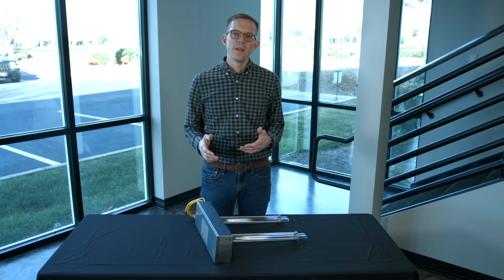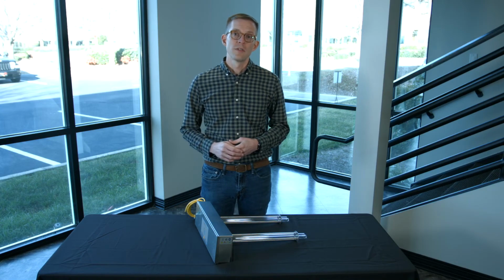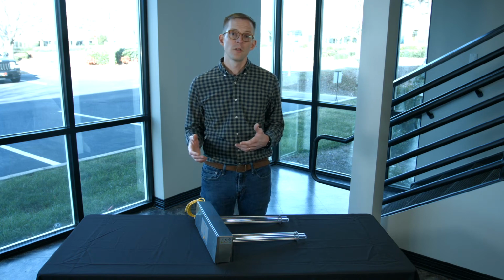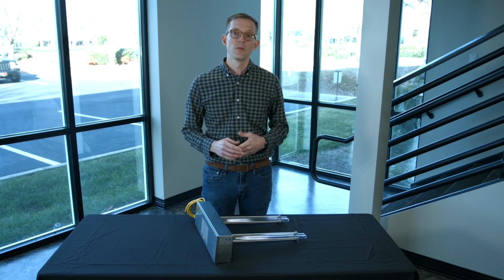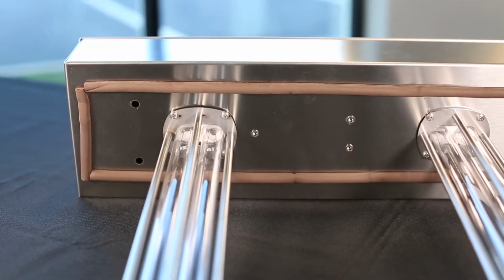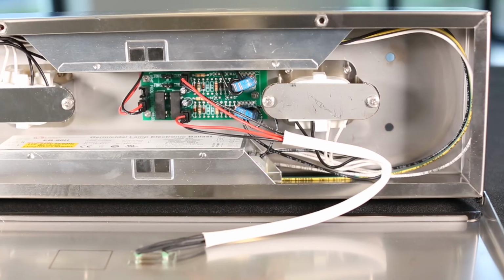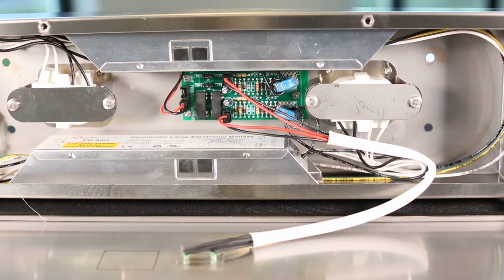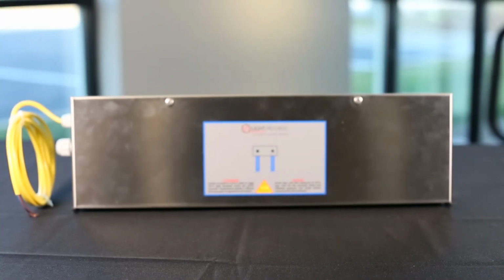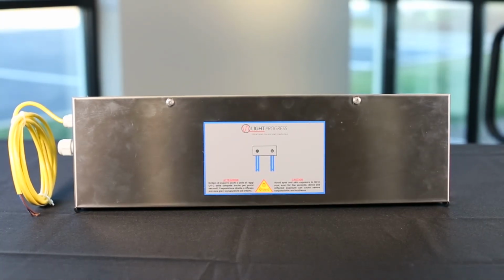If you're looking for a way to improve indoor air quality in your facility and reduce pathogen loads as the air flows through your HVAC system, the UV duct system is a great option to consider to get a high UVC dose that corresponds to the airflow moving through your system.